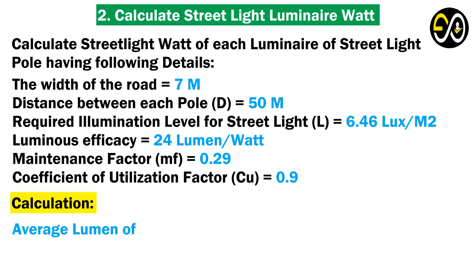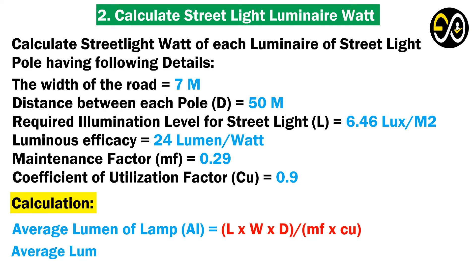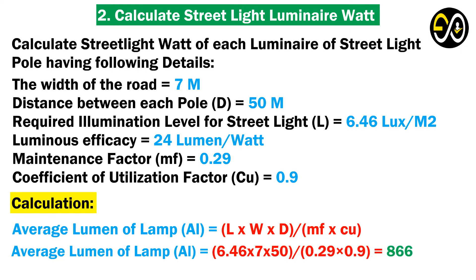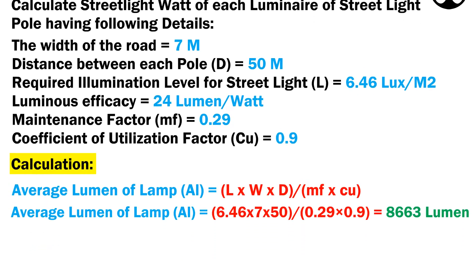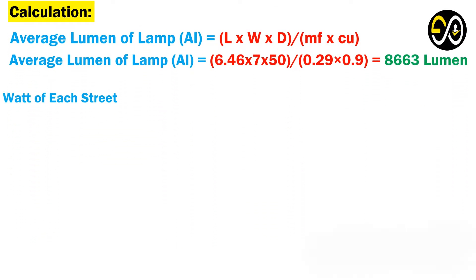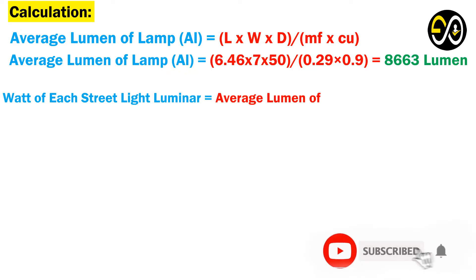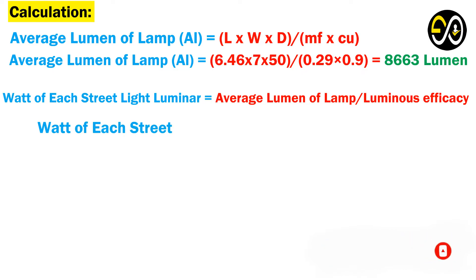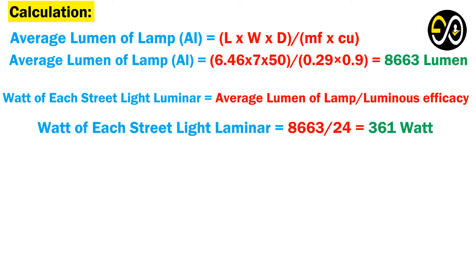Calculation: Average lumen of lamp equals L times W times D, over MF times CU. Average lumen of lamp equals 6.46 times 7 times 50, over 0.29 times 0.9, equals 8,663 lumens. Watt of each street light luminaire equals average lumen of lamp over luminous efficacy, which equals 8,663 over 24, equals 361 watts.